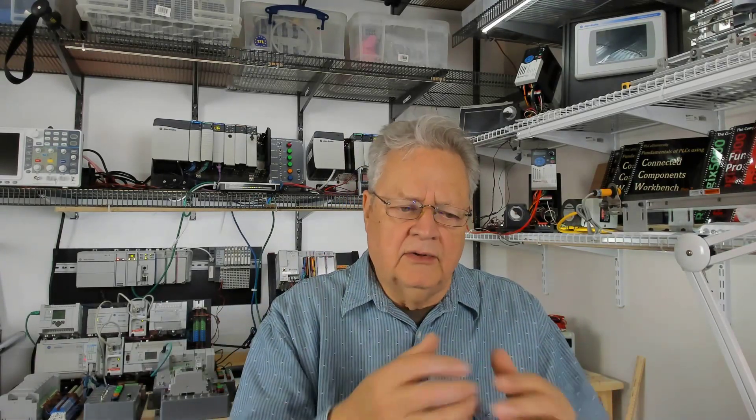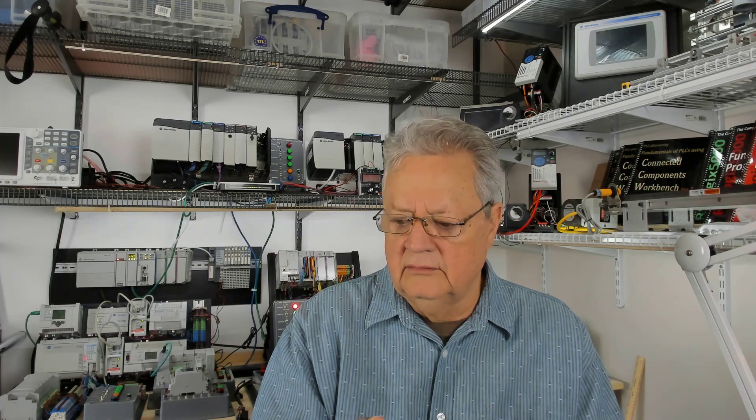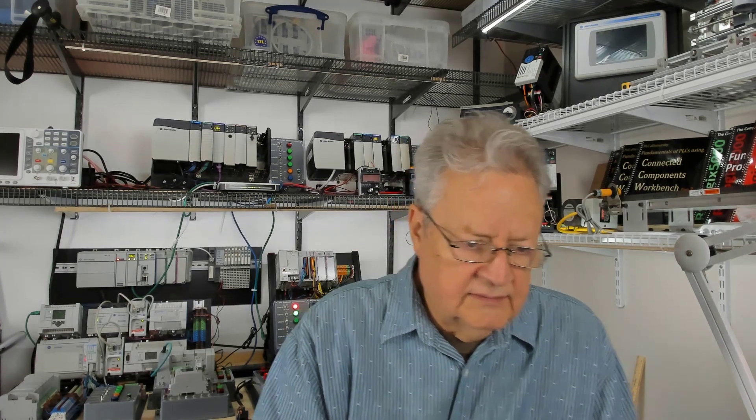We do this in a particular order. We try to do the conductors that are on the inside of the top of the box. Since we're working on it upside down, they would be the ones that go against the underside of the cover. And that way, as we add more conductors, we're not working in an entanglement. So there's a logical order to doing this. I've built hundreds of these. So after a while you kind of learn to do it with the least amount of grief. Let's get at this.